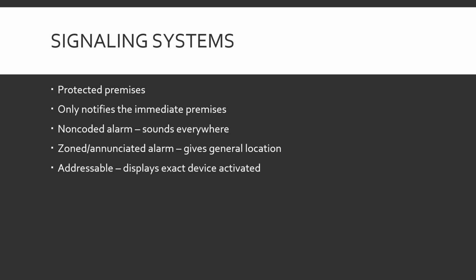Zoned/annunciated alarm. It's better. It gives more of a general location. Someone pulls the fire alarm in the gymnasium, and the gymnasium is in the west wing of the building. The little annunciator panel when you walk into the building, or the control panel, will say fire alarm, west wing. All right, we don't have to search the whole building, but we're still going to have to search a hallway, a bunch of rooms, that kind of thing.